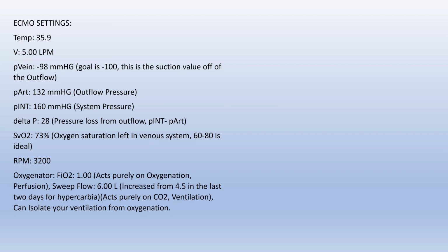This particular oxygenator had an FiO2 of 1.00. Again, that means basically all of the hemoglobin that's going in should be 100% hit by that oxygen. This sweep flow, again, we're not going to get into the nitty-gritty details of this. What you need to know, the higher the sweep flow, the better you are at clearing the CO2, right? So it's important not only to oxygenate the patient, but to clear off the CO2. And this is another thing that's very interesting with ECMO. Because you can closely titrate your FiO2 as well as your sweep flow, you can independently titrate your oxygen pressure within your system, as well as removal of CO2 within the system.